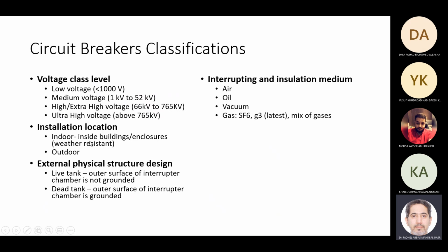Classification based on their location: sometimes they are called indoor breakers and outdoor breakers. Based on their external physical structure design, we have live tank and dead tank. Live tank is where the interrupter, the contacts location, is not grounded. Dead tank is where the chamber in which the contacts are located is grounded, it's connected to ground. I will show you later.